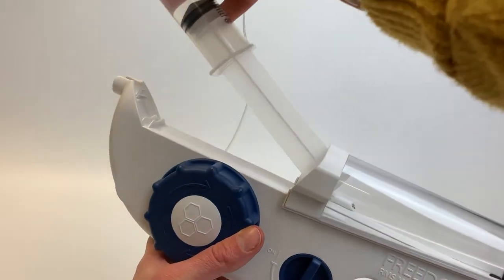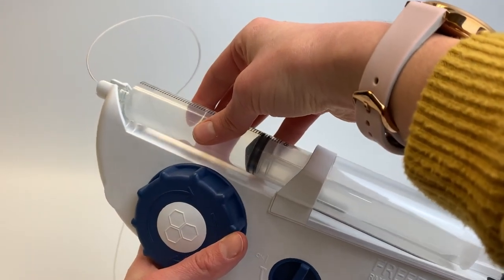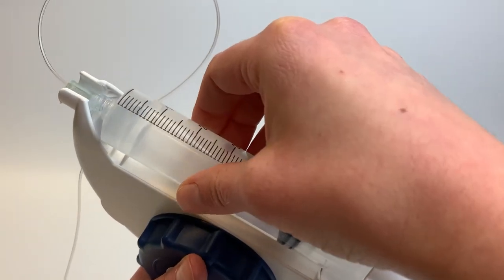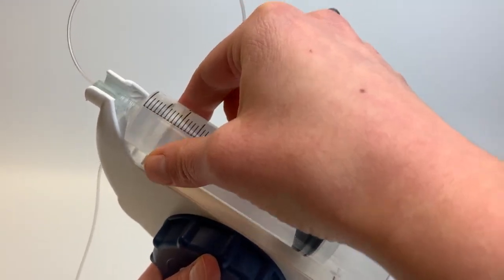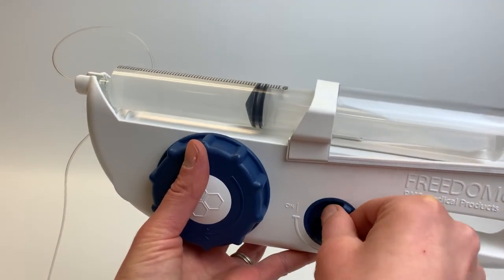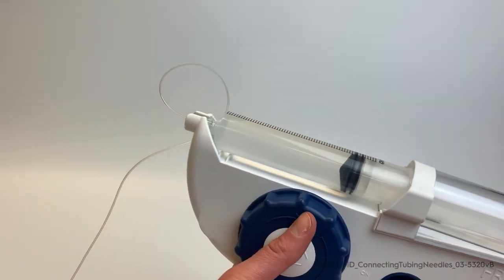If using the Freedom 60, note that if you accidentally connect the high flow needle set directly to the syringe without the precision tubing, the syringe will not stay in place and may eject from the syringe driver.